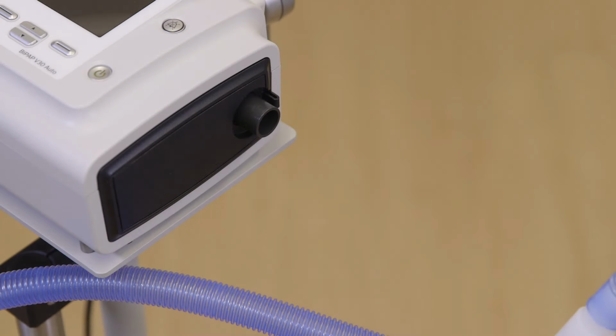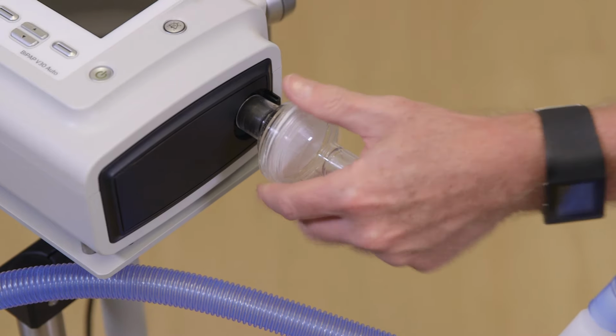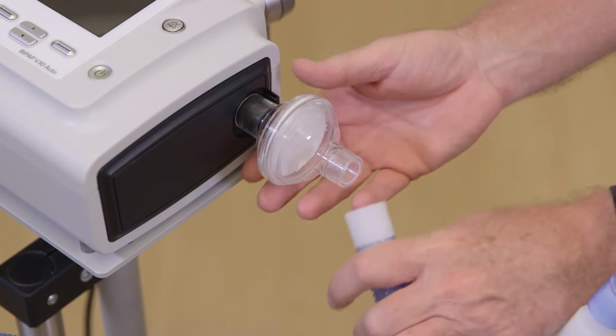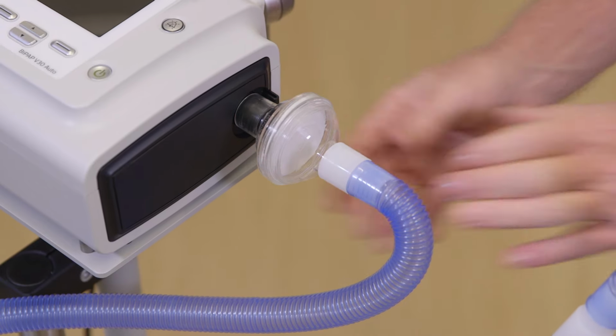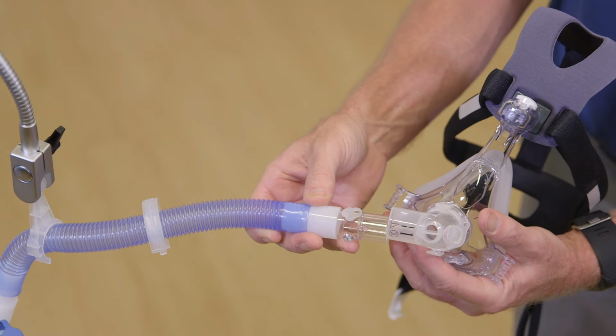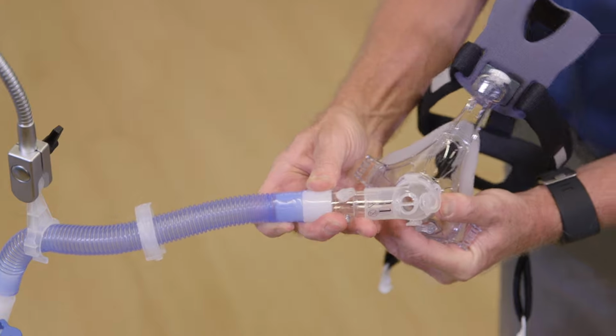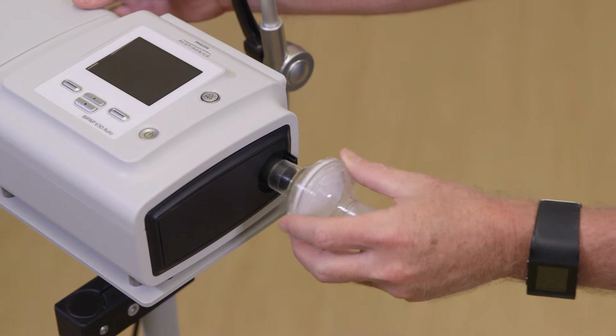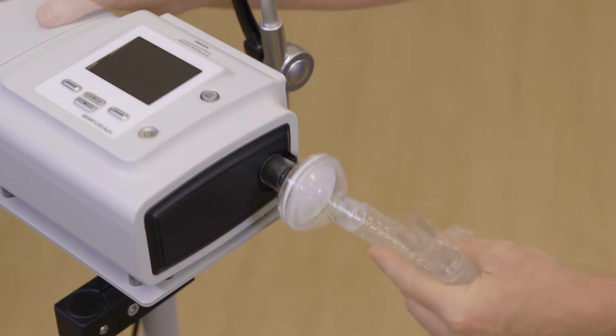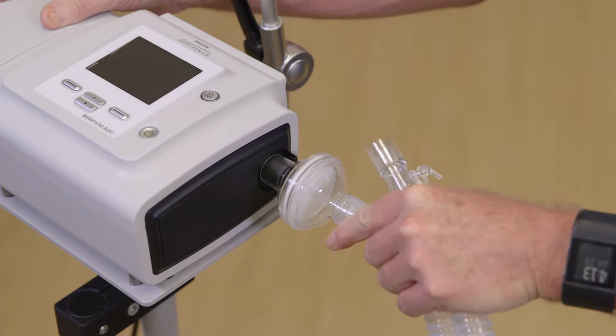To use humidification, connect the bacteria filter to the device air outlet and then connect it to the humidifier. From the humidifier, connect the circuit to the patient mask selected. If not using a humidifier, place the bacteria filter between the device air outlet and patient circuit.